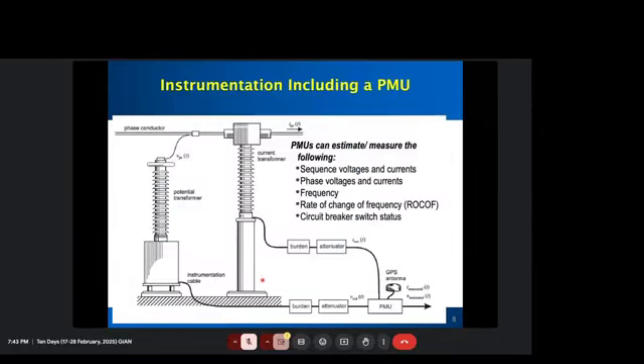So a little bit more about CT and PT - how they look and how they're connected to the PMU. You have a potential transformer, and it will have a lot of components because it is connected to high voltage. High voltage is applied on the primary side, and then the secondary side is very low, like a 1000 to 1 or 500 to 1 ratio. The ratio is decided based on what the high voltage line is - if it's 132 kV versus 500 kV, or even higher, you have to increase the ratio to get the lower voltage and low current out.